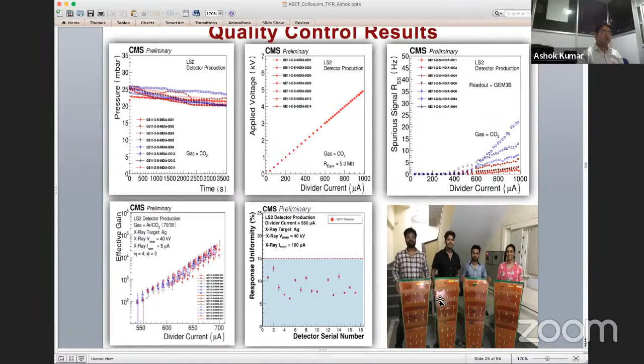And the other one is the effective gain. This is the actual measurement of the gain we do using the X-ray source, and we found that all these detectors have 10⁴ to 10⁵ gain at 750 microamps, so bias voltage of say 3600, 3700 volts. And since we have different sectors in the detector, if we have 24 sectors, then we can see the response uniformity, the gain uniformity: the gain is varying within 15% in all these sectors. And then these guys are happy after producing these detectors, because these detectors are ready for the shipment. So the detectors are packed and sent to CERN.